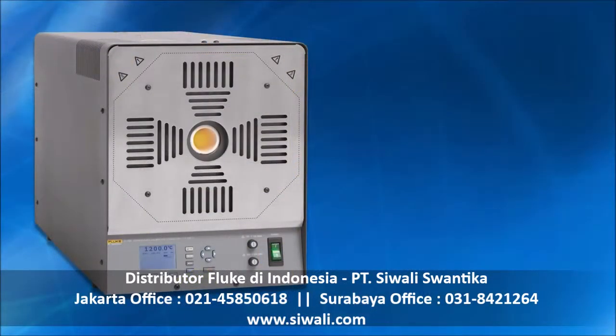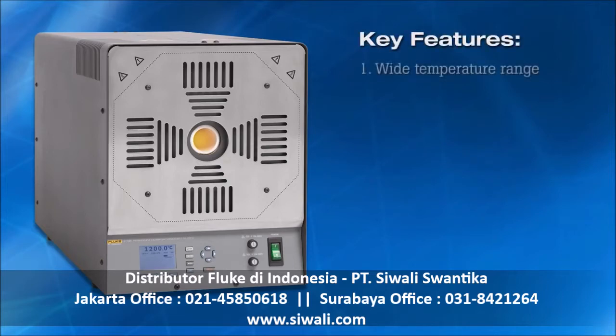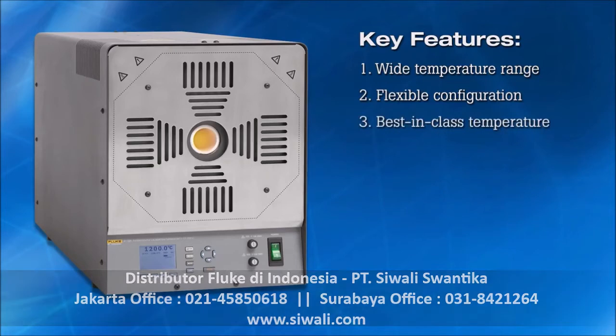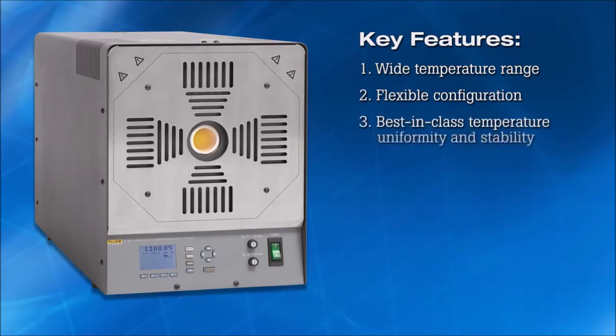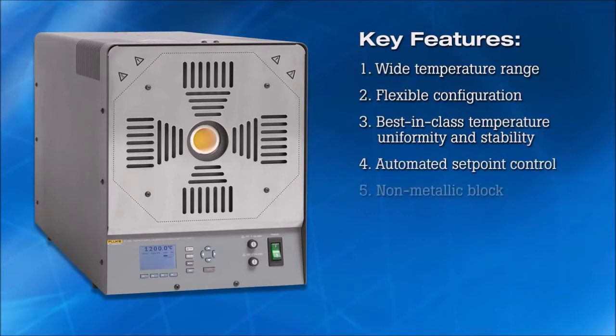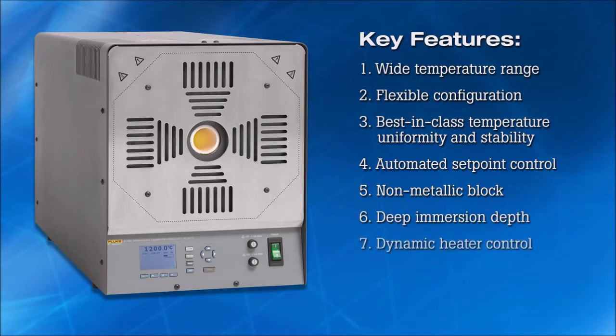The 9118A is designed to meet the most demanding requirements of high-temperature thermocouple calibration. There are 7 key features that distinguish the 9118A from other high-temperature calibration furnaces. 1. Wide temperature range. 2. Flexible configuration. 3. Best-in-class temperature uniformity and stability. 4. Automated set point control. 5. Non-metallic block. 6. Deep immersion depth. 7. Dynamic heater control and cutouts.